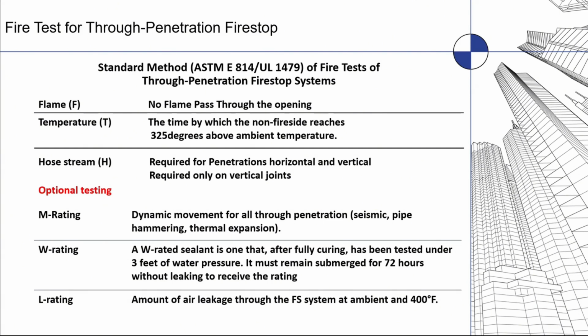The next would be, depending on the type of test, whether or not there would be a temperature measurement. In different cases, depending on the type of test, this temperature would be measured to determine how much it grew from the hot side where the oven is onto the cold side, to make sure it didn't reach a temperature rise that would create a failure point of the test. And all of these are done to some kind of time frame. The time frame would be something like 1 hour or 2 hours or 3 hours. And for that duration, if there's no flame showing for that 1 hour or 2 hour or 3 hour test, then that passes. Same thing with the temperature. The temperature would have to not rise above a certain point, in this case 325 degrees, in that 1 hour or 2 hours or 3 hours, depending on what kind of test.